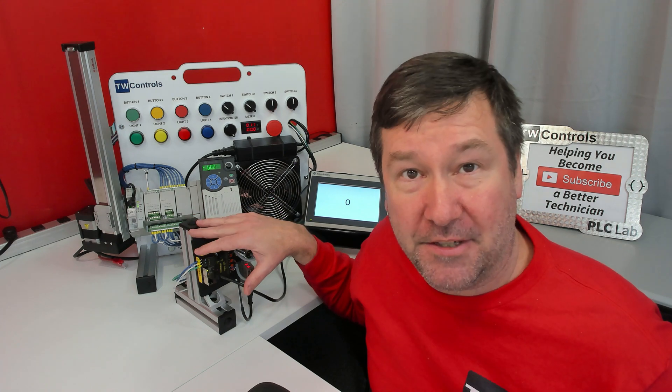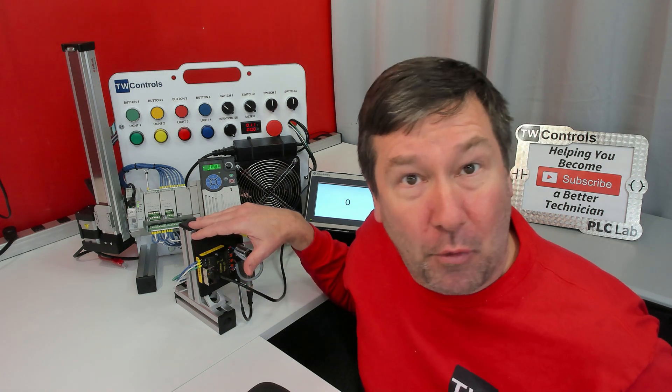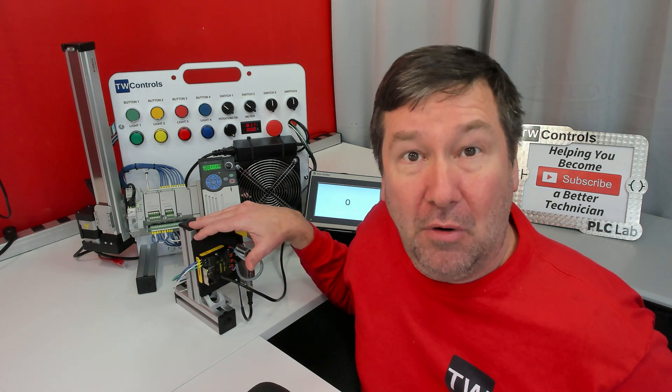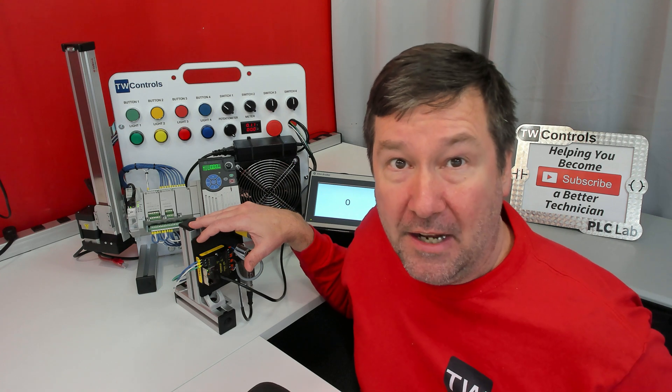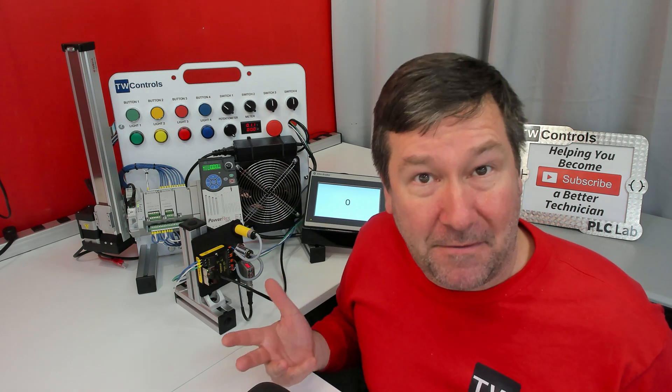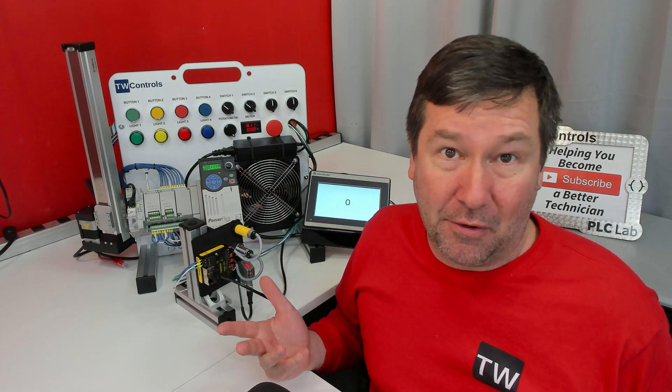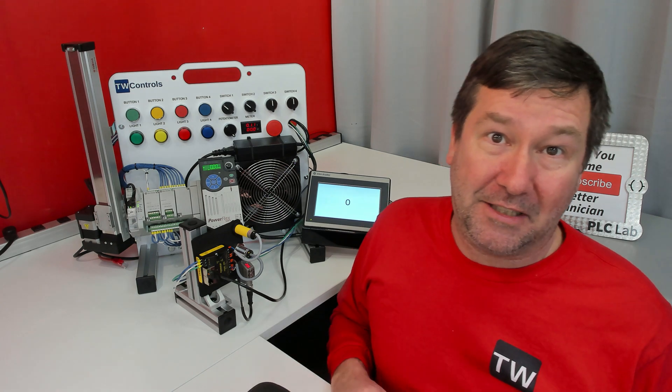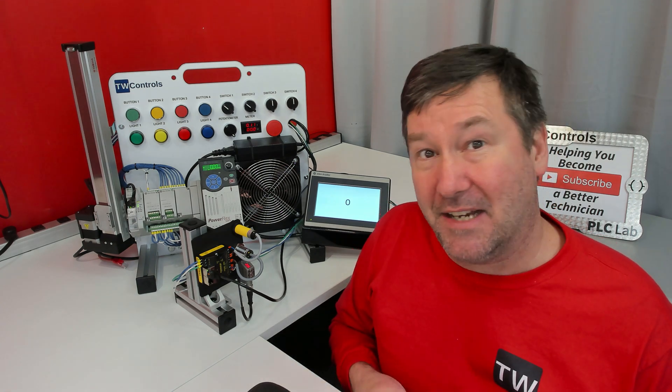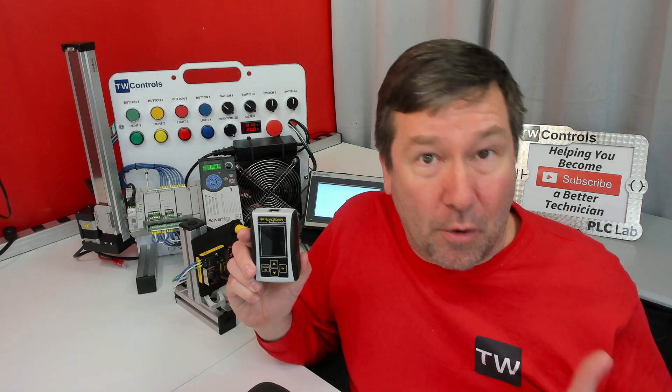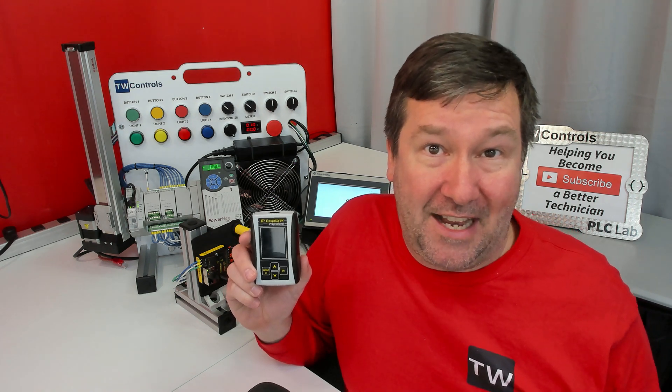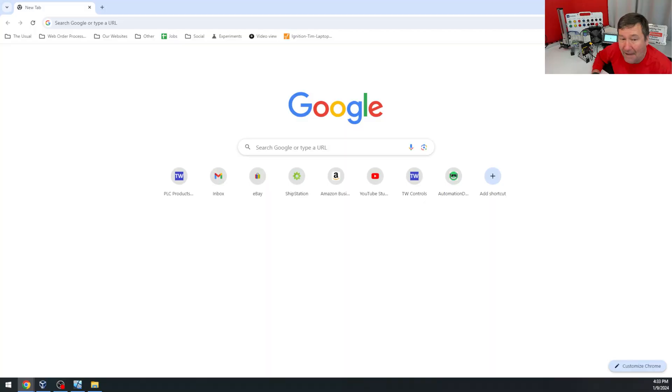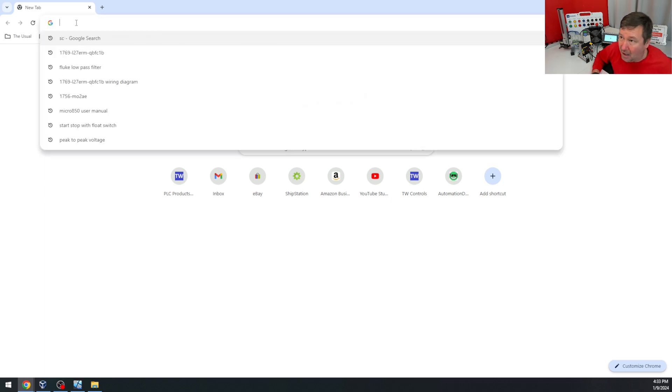We've already configured the IP address of your IO-Link module for 192.168.1.15, and if you happen to be following along with this video to configure your IO-Link device, it has DHCP enabled by default. You can take our SIM IPE or another DHCP server and assign an address. After that, this is probably the most intuitive module as far as getting it set up.